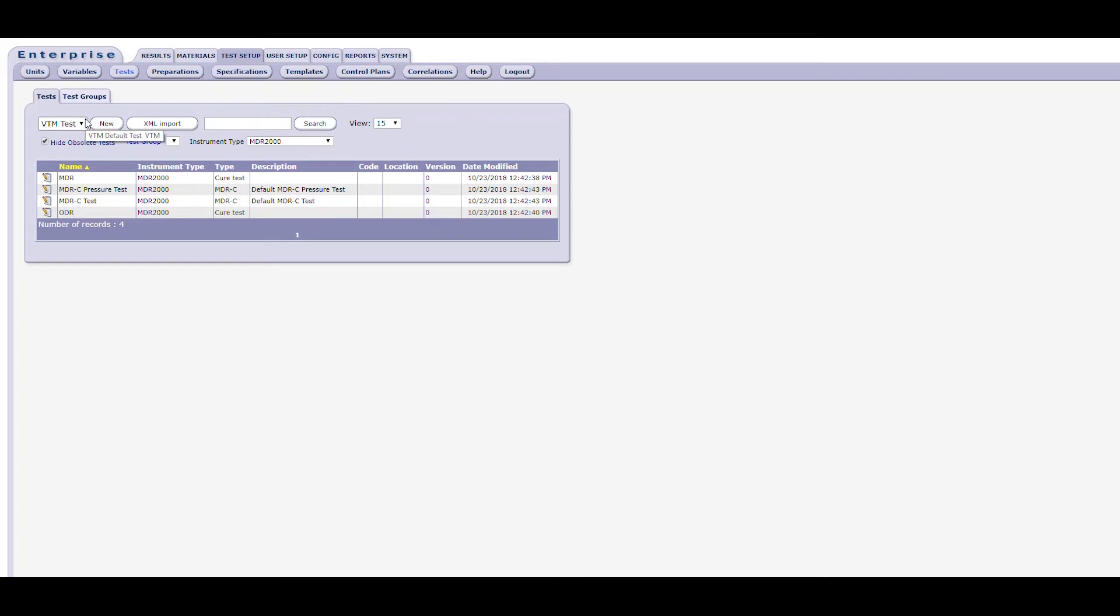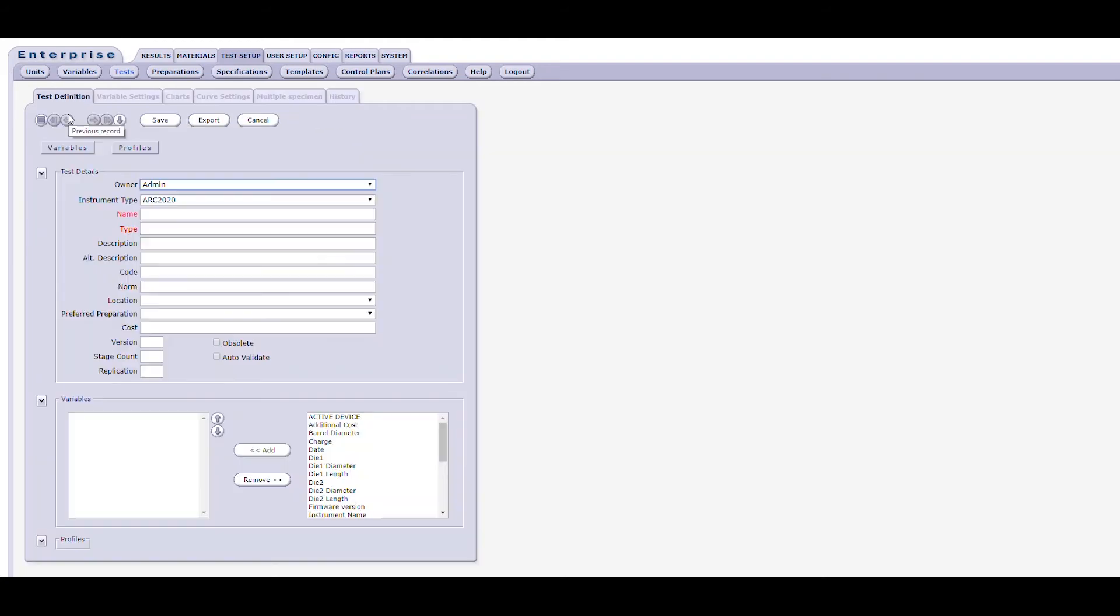The test creation process will take you through four forms: test definition, variable settings, charts, and curves. In some cases, depending on the instrument type, there may be an additional form for multiple test methods. After clicking the new button to start the process, you will be limited to using only the test definition form until after some basic defining information has been entered and saved.